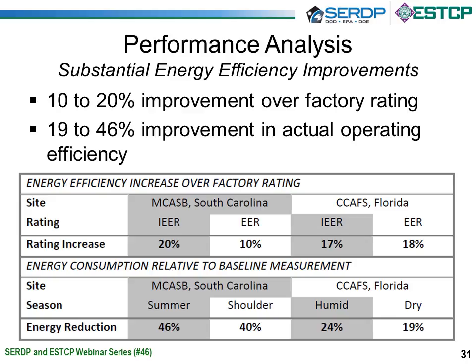The other thing is we measured compressor discharge temperatures and compressor case temperatures that were about 30 degrees cooler. So the compressor is running significantly cooler than it does without Climostat. And we think those two things are going to actually increase compressor longevity, but we don't have long enough or enough data to really be able to say for sure yet.